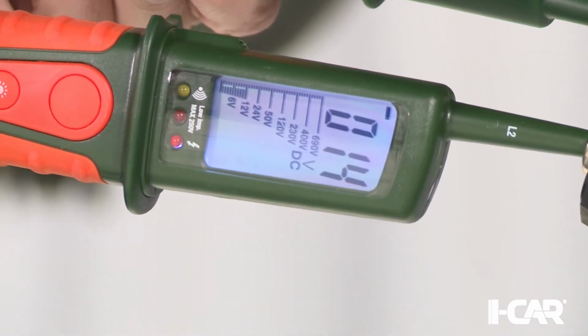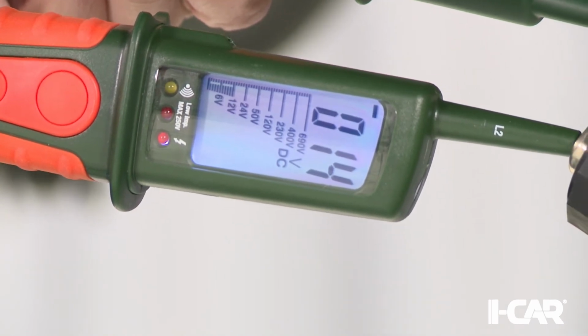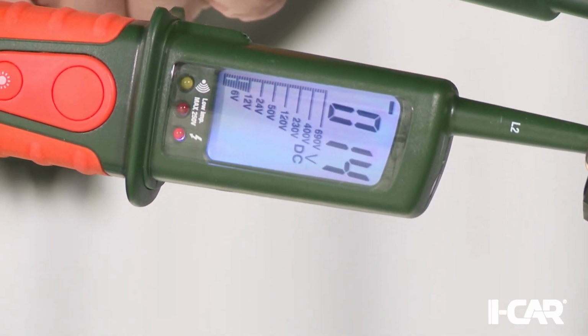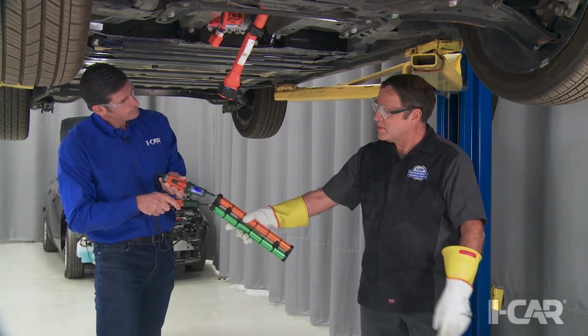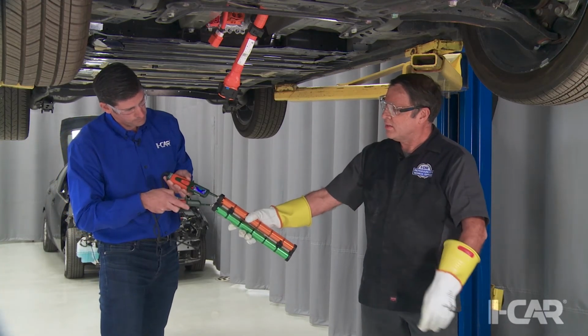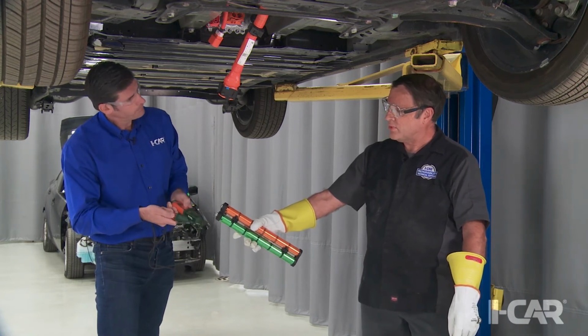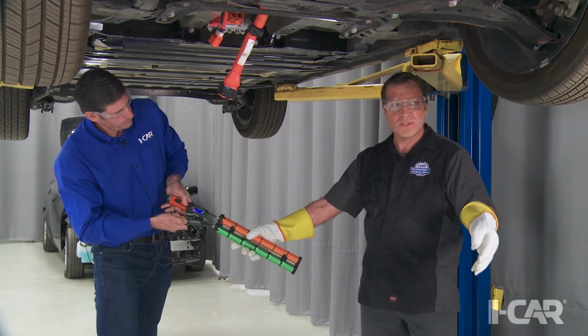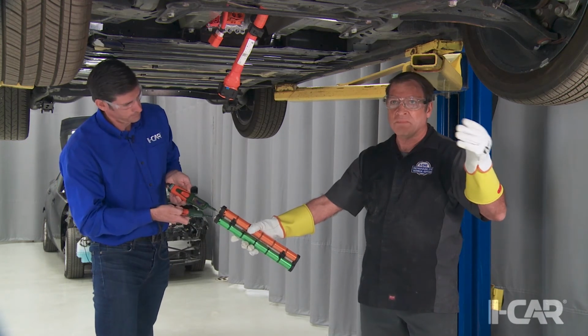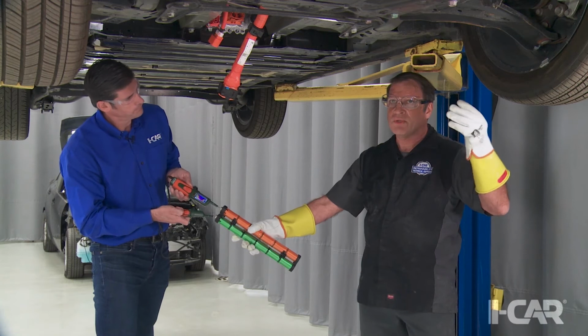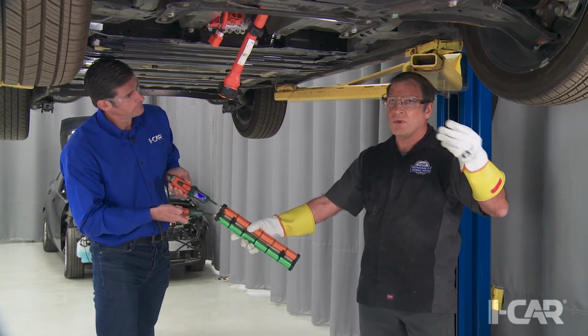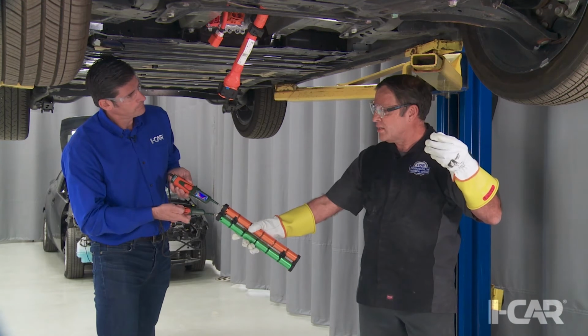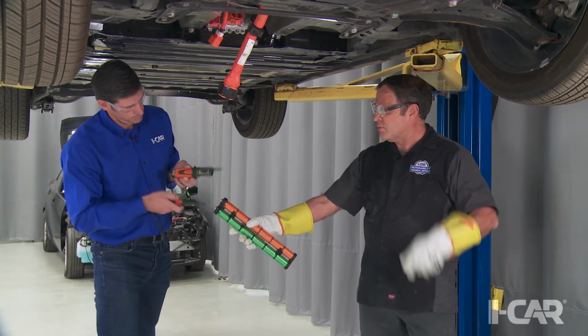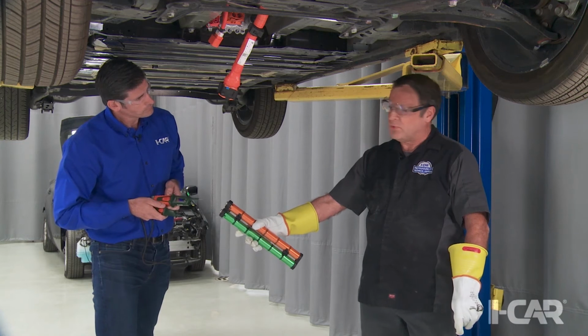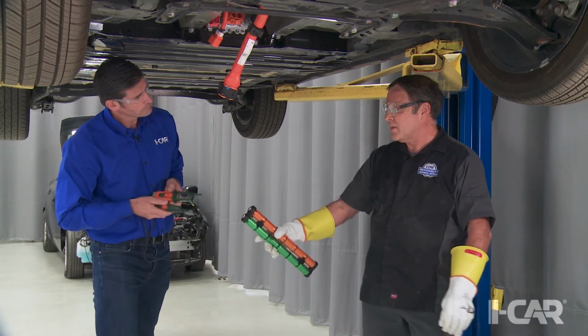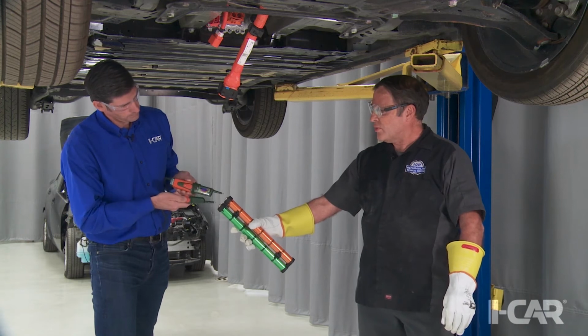So he's now verifying 14 volts, there is voltage there. Something neat about these 2-pole testers is that there's a button on each handle he can push while measuring voltage, which loads the circuit slightly. If there's any ghost voltage or stray voltage floating on the wires, that load helps dissipate any charge. It's not meant to discharge high voltage capacitors, but it gives us more assurance of the reading we're seeing.